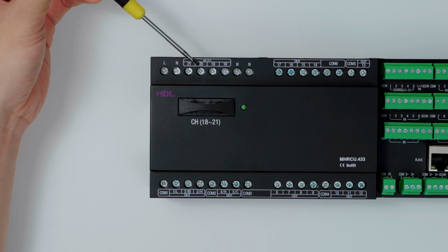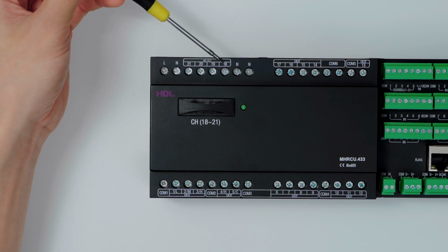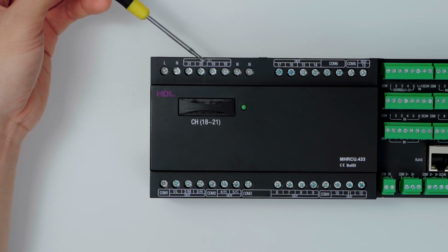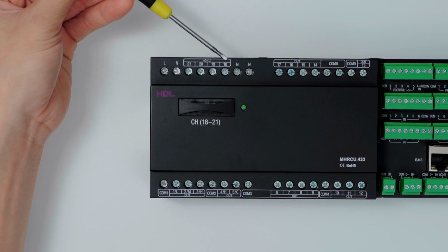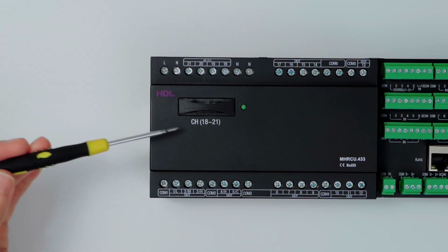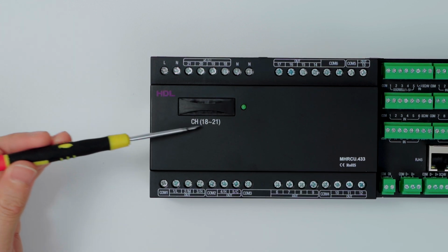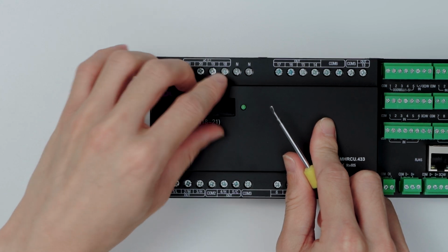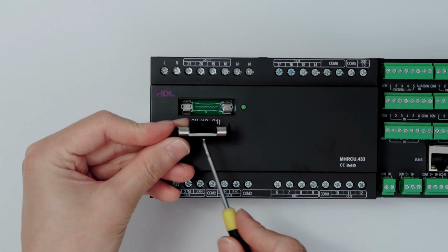Finally, there are interfaces with dimming symbols 18, 19, 20, 21 that support 4 dimming circuits, which can be connected to leading edge lights. The neutral wires can be combined, but each live wire needs a separate connection. In the middle of these interfaces, 18 to 21, there is a fuse socket for the dimming circuits. If any of the fuses blow, you can easily replace them by removing the fuse seat.